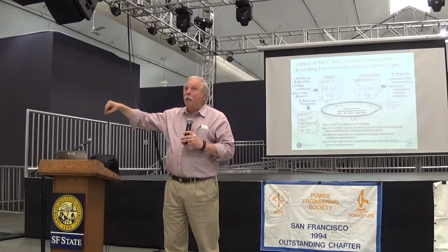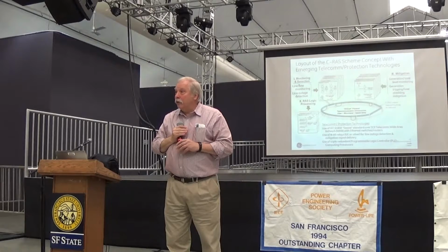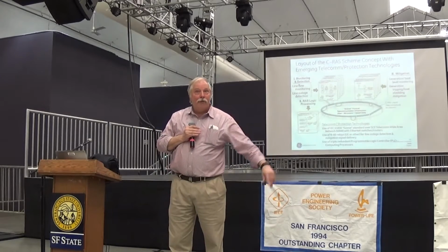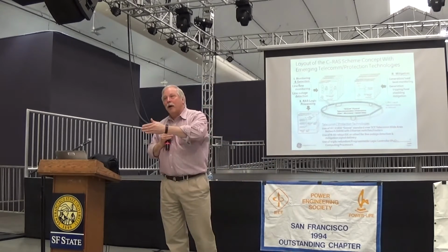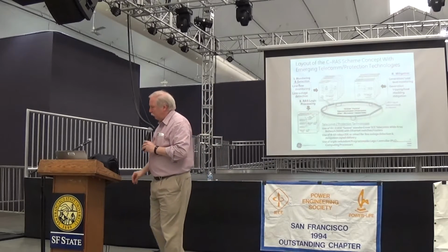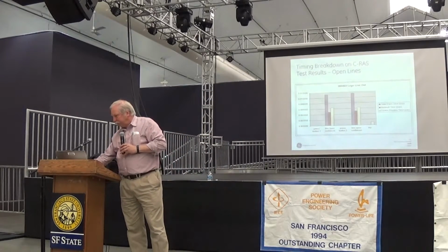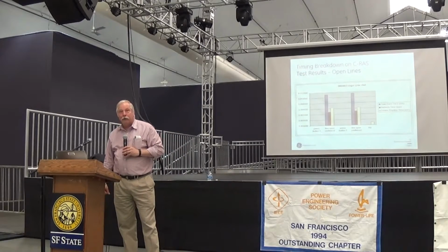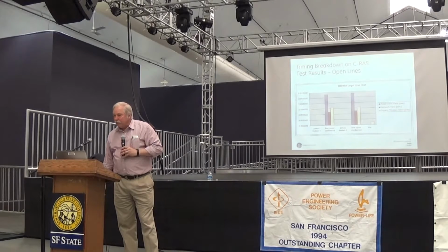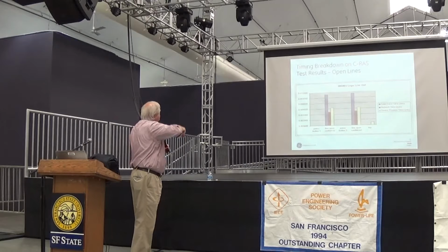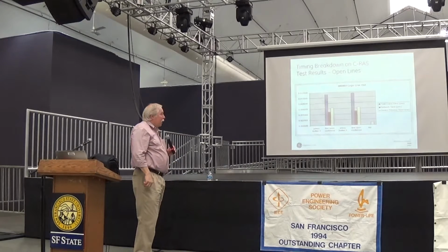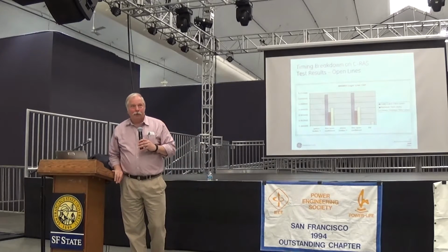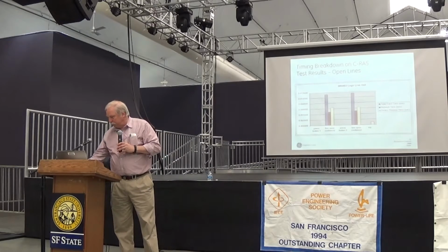Same thing happens on the output side. An output Goose message is sent to do the mitigation or the tripping of loads or whatever the mitigation function is. Those are also defined in the CID file of the relay. Bottom line performance, these are actual measurements of a LUGO line out remedial action scheme. Round trip times, you see that the tall blue ones there are the round trip communication times on the order of 11 to 12 milliseconds. Round trip over 600 miles right now in these remedial action schemes.